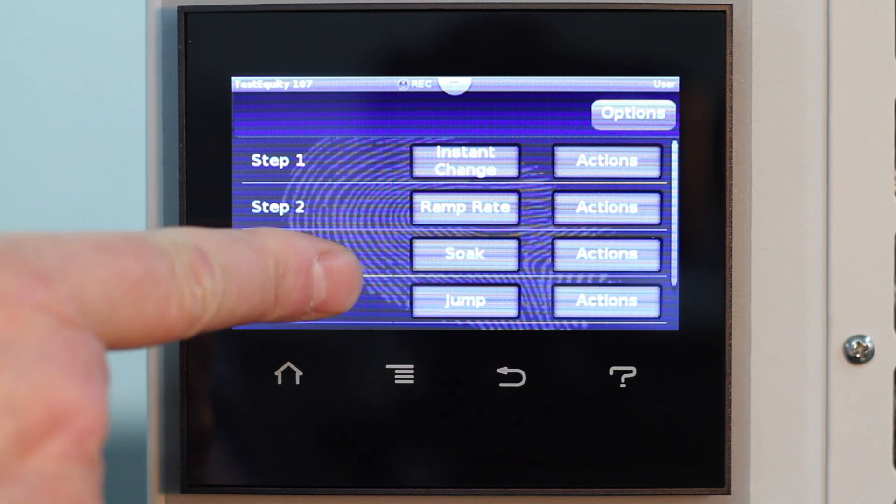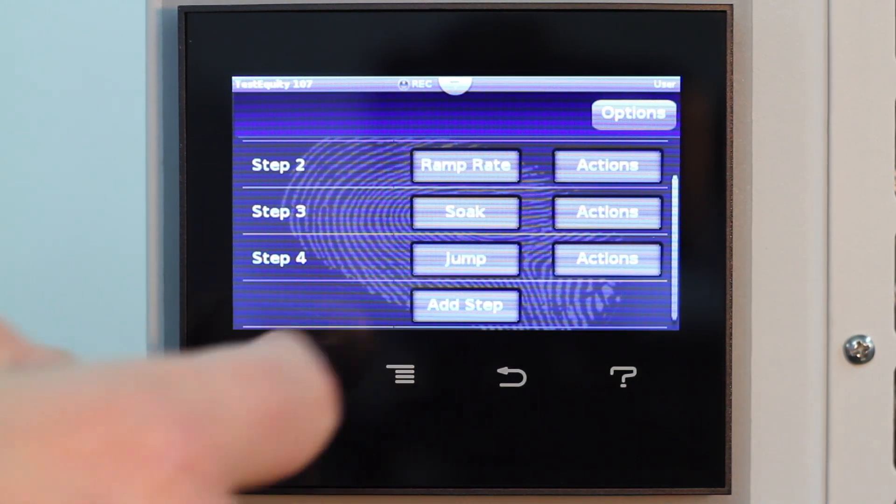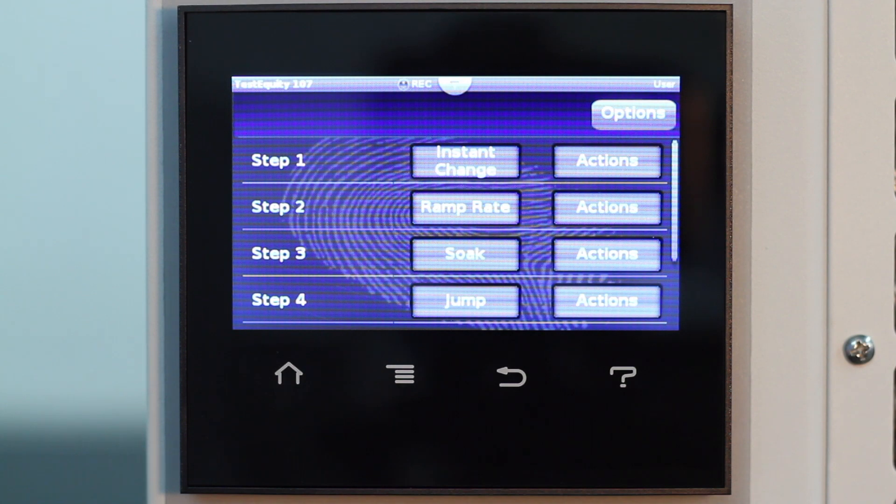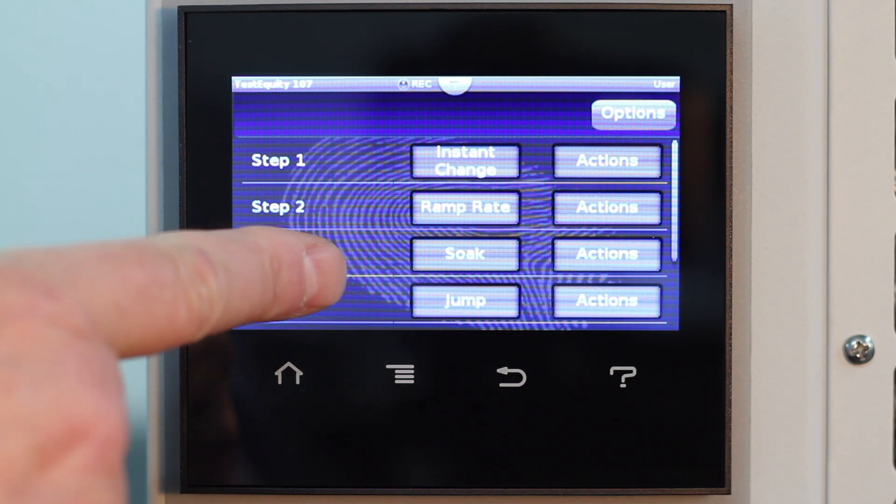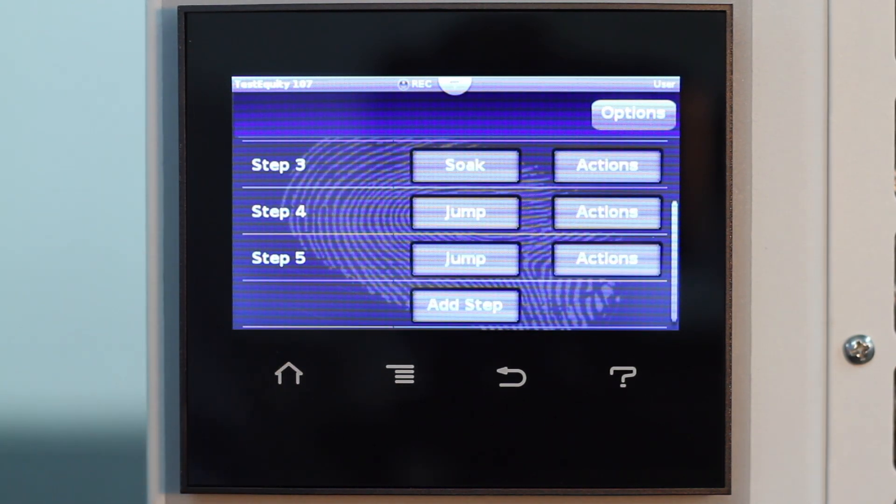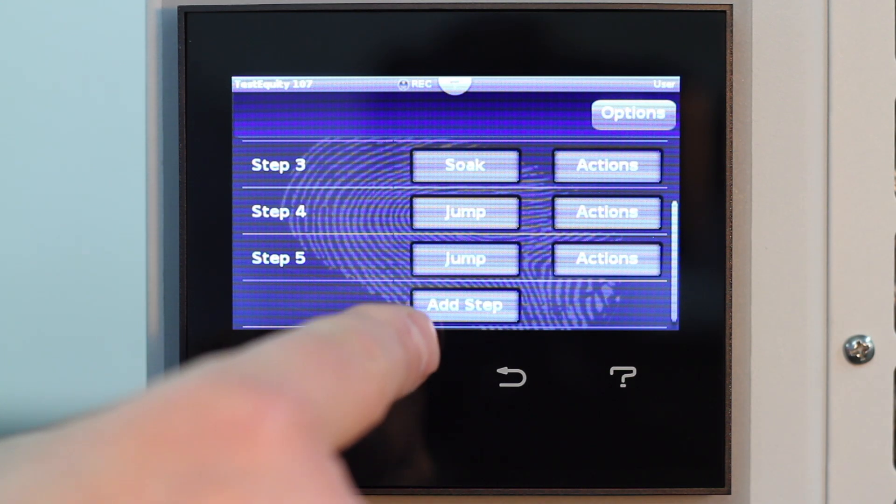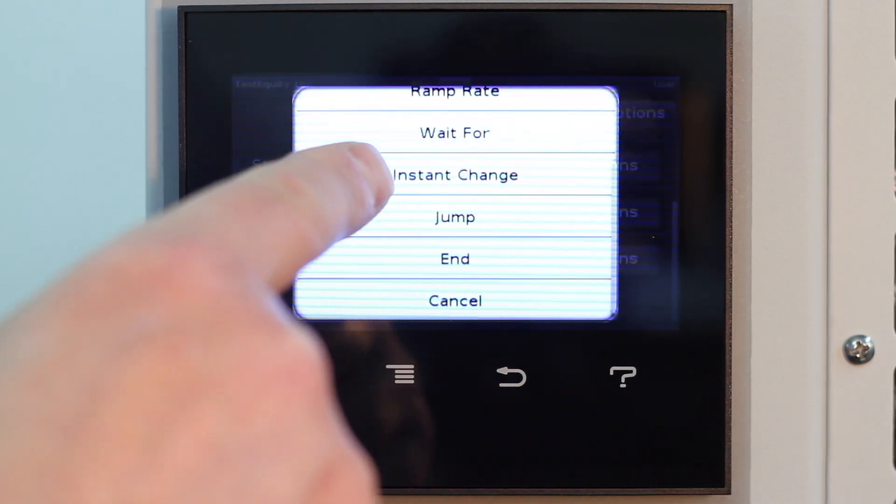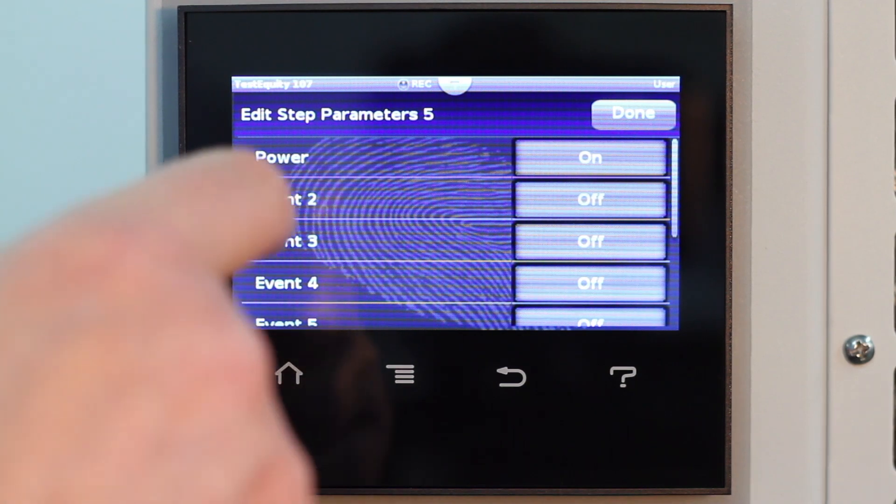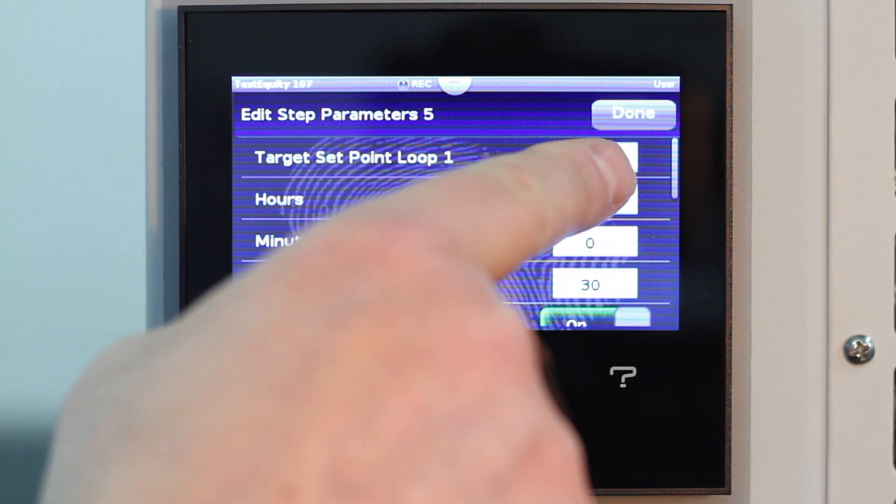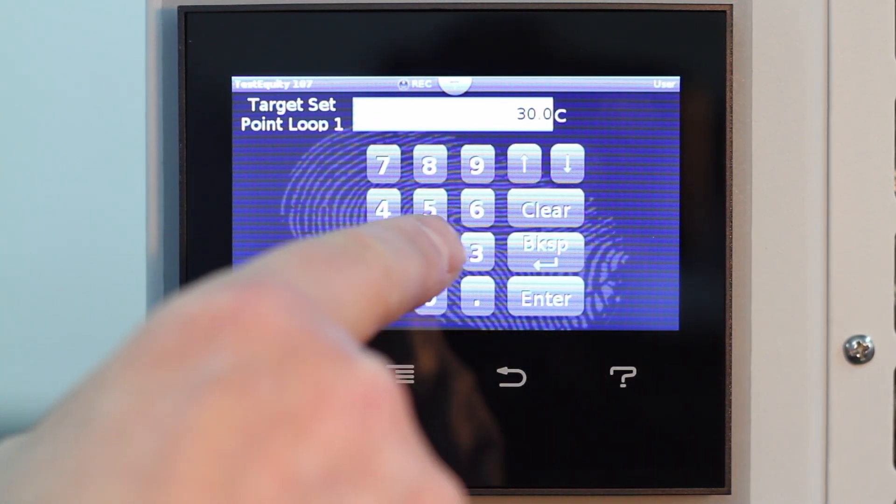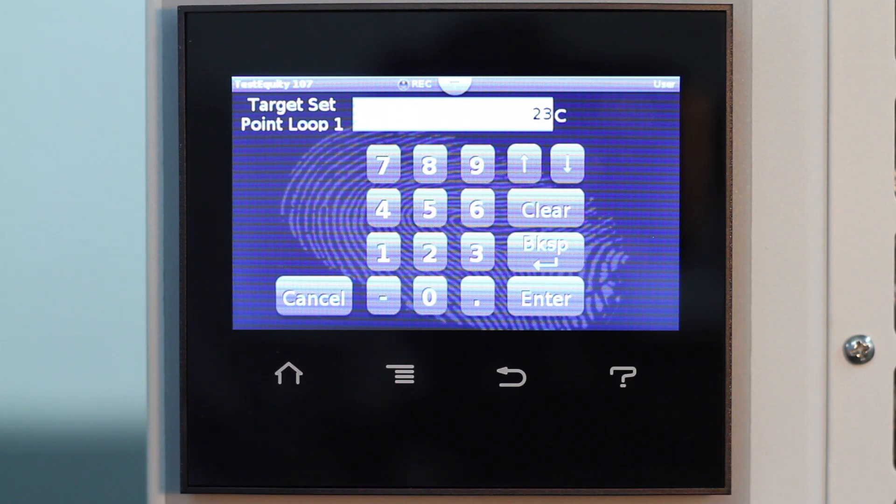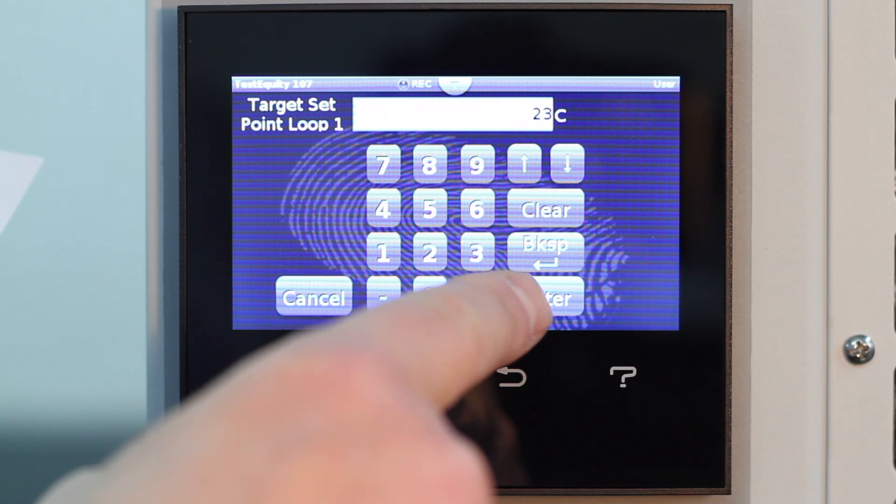Step 5. Go to 23 degrees C as fast as possible. Wait for the chamber temperature to reach 24 degrees before advancing to the next step. For Step 5, we use an instant change type and enter 23 degrees. The controller automatically picked up the last instant change parameters, so we only need to change the temperature in this instance. We will keep the other parameters.